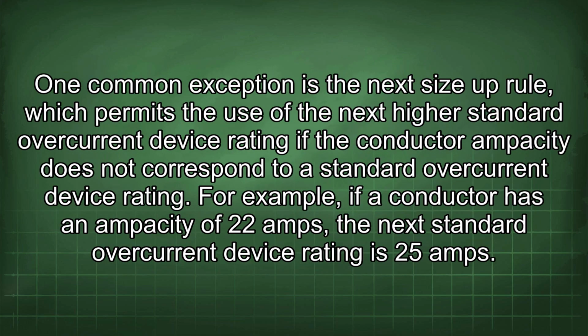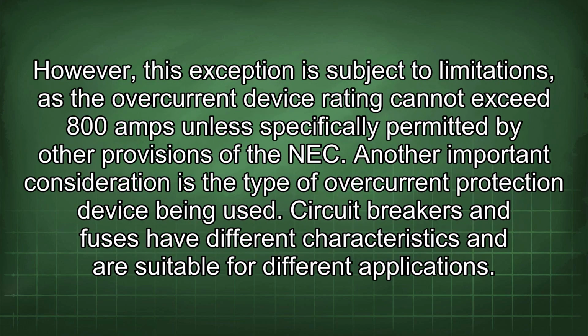One common exception is the next size up rule, which permits the use of the next higher standard overcurrent device rating if the conductor ampacity does not correspond to a standard overcurrent device rating. For example, if a conductor has an ampacity of 22 amps, the next standard overcurrent device rating is 25 amps. However, this exception is subject to limitations, as the overcurrent device rating cannot exceed 800 amps unless specifically permitted by other provisions of the NEC.